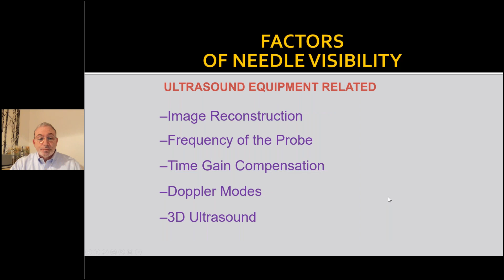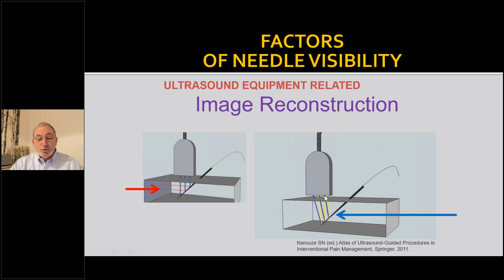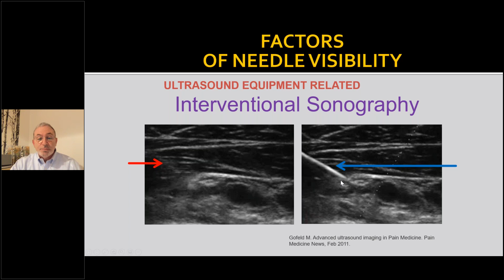Another way to improve needle visualization with equipment is image reconstruction. This is the normal ultrasound beam, reflected essentially at 45 degrees, but there is a technology which allows you to steer that reflection towards the probe, and that allows better needle visualization. Most contemporary machines have this technology incorporated, but in some machines you can turn it on and off. So here's the example. You go here, you don't really see the needle. You turn on this needle steering beam, and it comes up and you see it.